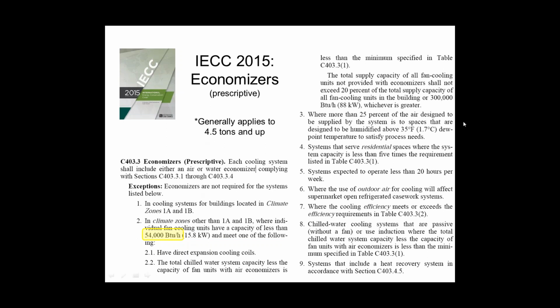There are some exceptions to that. They're not a big deal. Most of them are related to either process applications, like note number 3, residential high-rise buildings, like note number 4, or churches, like note number 5. Those are the ones that will typically come up for you. Pretty much everything else you're going to have to do it. Process, hardly ever use spaces like a church area or a high-rise residential. You won't have to do it. Everybody else is probably going to be in a scenario where they got to put an economizer on their rooftop, on their split system, on their fan coil, on their air handler, on their water source heat pump. It doesn't matter. If it does cooling and it's 54,000 BTUs, it has to have an economizer.